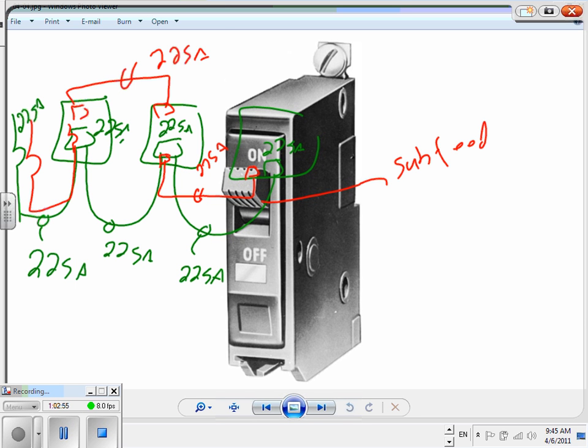So the difference, guys, here's what the difference is. Can you see the current? The current here goes in, and this panel only sees, if it's a subfeed, the current that's consumed by it. If it's feed through, look at the current, it's going to go through each and every one of them, right? So if I have a lighting fixture here, the current that's feeding this lighting fixture is actually seen by each and every one of these panels. So they have to be the same size, basically.